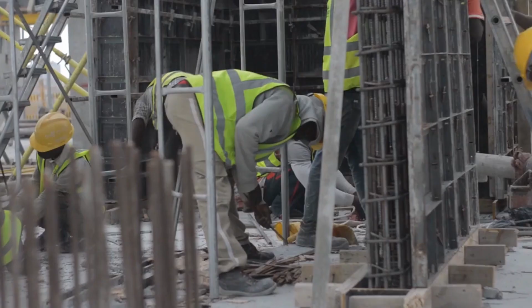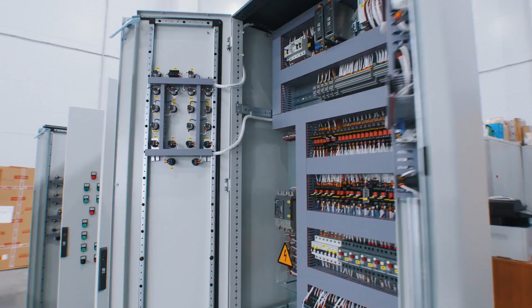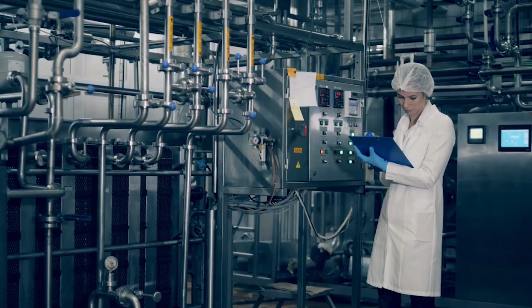Your equipment supply contracts will be lacking critical factory test requirements, meaning that defects that should have been identified and fixed in the factory cause delays during commissioning while errors are fixed. And equipment supply contracts for automation control cubicles need special attention to ensure integrated testing of both the hardware and the software is clearly defined in procurement contracts so that these issues are not deferred to site testing, which always causes significant delays while groups try to troubleshoot why the control systems are not functioning correctly.